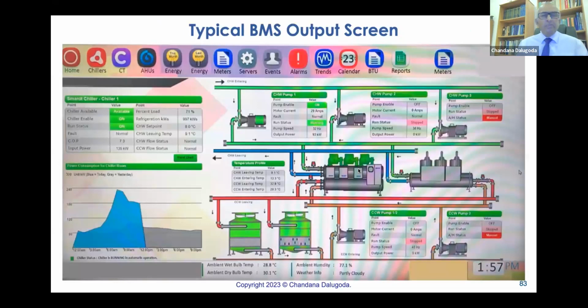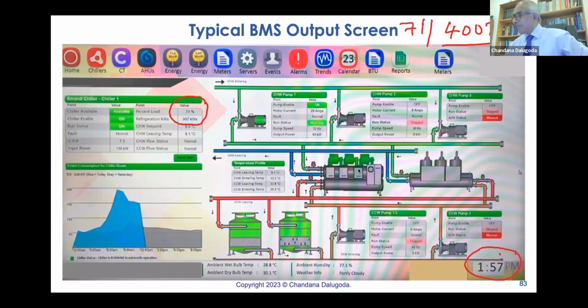Now this is the BMS output screen. I took it on a very sunny day, time almost 2 o'clock, where it is Ceylon Towers. Now, originally we had, as far as I can remember, 350 by 350, 2 chillers working together, but not 700, maybe 600 tons. But in 2015 we replaced them with a magnetic bearing oil-free compressor chiller, 400 ton. A 400 ton chiller is working now for the entire building. But the great thing is at 2 o'clock, hot sunny day, the chiller is loaded only 71%. Thanks to BMS.